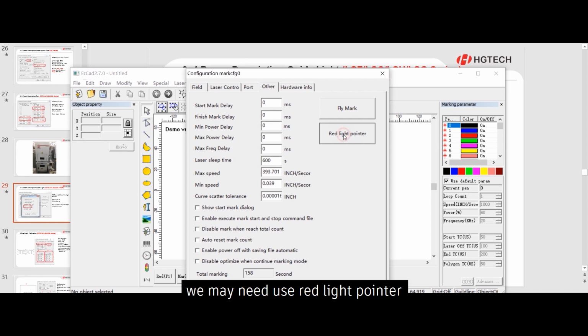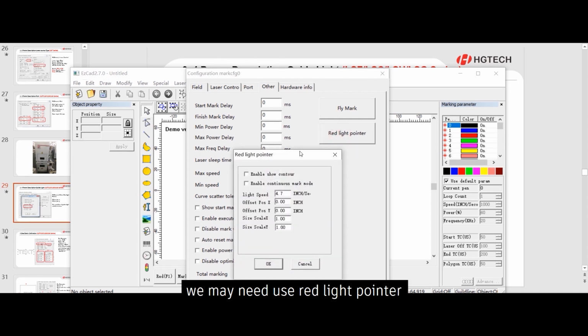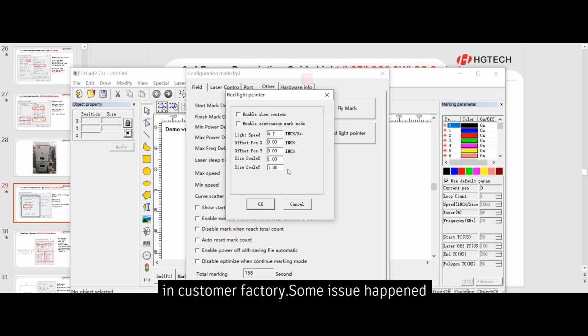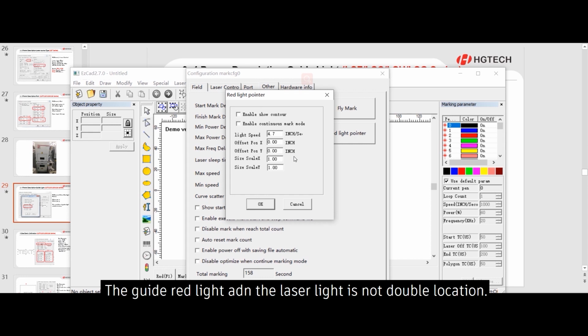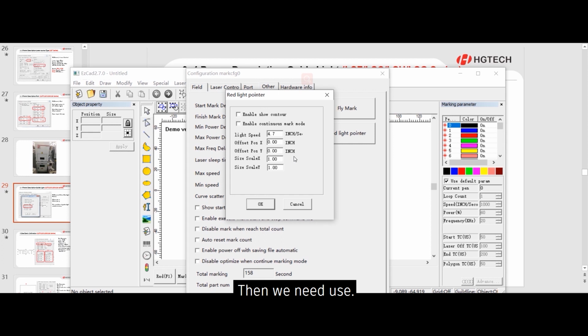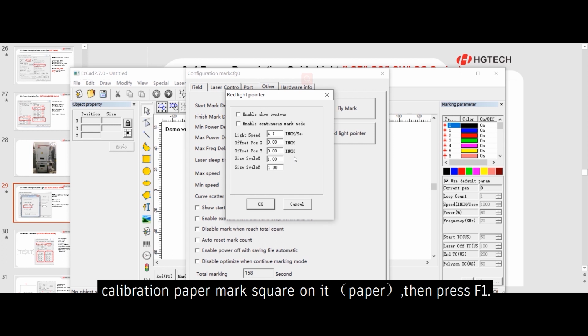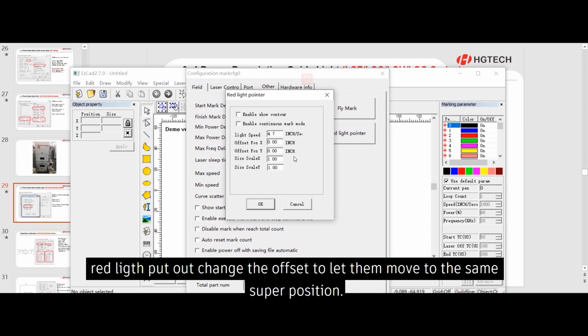Fourth window, we mainly use the red light pointer. In a customer factory, some issue happened. When they move the equipment a lot, the guide red light and the laser light do not overlap in location. Then we need to use calibration paper, mark a square on it, then press F1, and the red light is put out. Change the offset to let them move to the same superposition.